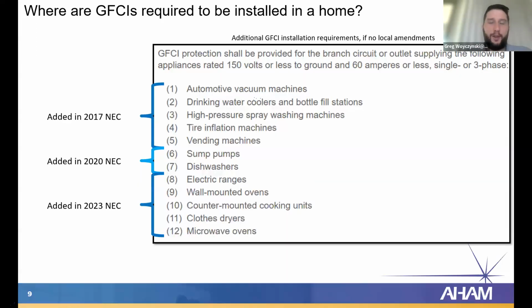So it doesn't end there. It's a little bit more complex. There's another section of electrical codes that require GFCIs for certain appliances. So it doesn't matter where these things are in the house. They must be connected to a GFCI. So in 2020, we saw dishwashers added. They must be connected to a GFCI no matter where they are in the house, according to the 2020 NEC. And then in the 2023 NEC, we see a major expansion. So no matter where you have an electric range in the house, no matter where you have a microwave oven in the house, a clothes dryer, according to the 2023 NEC, it must be connected to a GFCI.